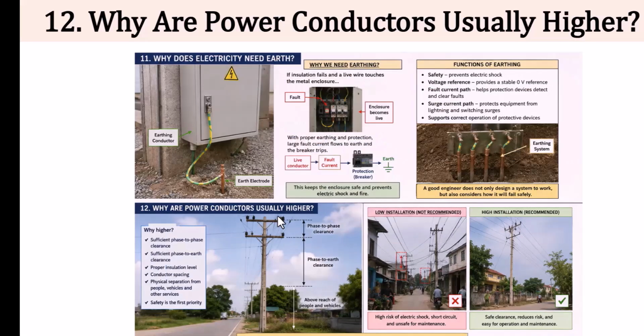Why are power conductors usually higher? Look at this arrangement. Why is higher voltage equipment generally kept high above normal human access? Think like an engineer. Why not install the medium voltage equipment only 2 meters above the ground so maintenance becomes easier?